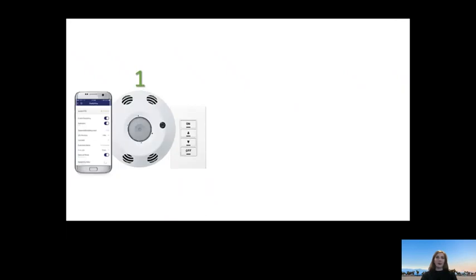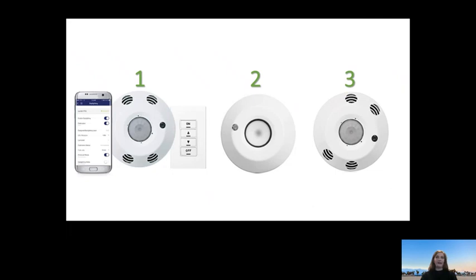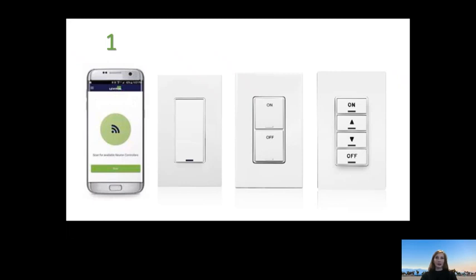What composes the Provolt control system? Firstly, the Room Controller app, which offers quick and easy room configuration and testing with the use of a smartphone. This control system has a zero commissioning option for the 01C through 4C models by utilizing dip switches on the back of the devices. But it also has a separate Bluetooth to configure option for the 5C and 6C models for commissioning and programmable applications. The line voltage photocells, which are self-contained mini daylight harvesting systems offering the functionality of a 0 to 10 volt dimming photocell. And then we have the line voltage sensors, which combine the line voltage occupancy sensors and photocells into a singular self-contained unit as well. Let's take a closer look at the Provolt control system components.